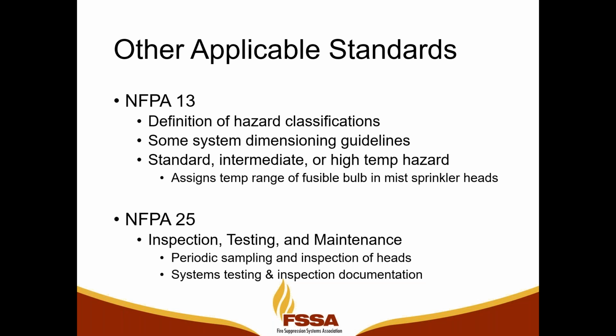Also, NFPA 25 does have some parts that talk about inspection, testing, and maintenance. It deals with things like periodic sampling and inspection of heads, system testing, and inspection documentation, but it's mainly to deal with water-based systems. So there are some things within NFPA 25 that water mist systems have to follow under the inspection, testing, and maintenance guidelines. Next slide.